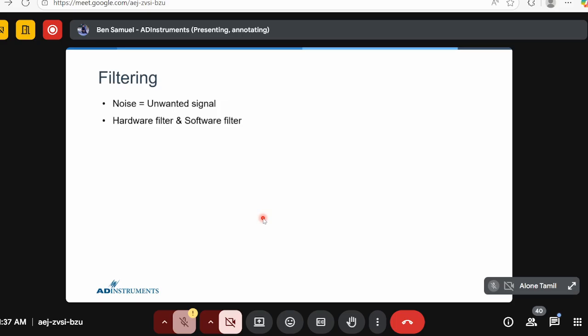For example, there's a hardware filter called the mains filter. You already know it is just to eliminate the 50 hertz mains noise. Once it is set, it is set. You cannot revoke the settings after signal data acquisition. So when you are acquiring raw data, you have to be very clear and precise. You should have a better understanding of the signal morphology and whatever filters you are going to set. The software filter is nothing but post acquisition. If you want to do any filtering, you can still do that.